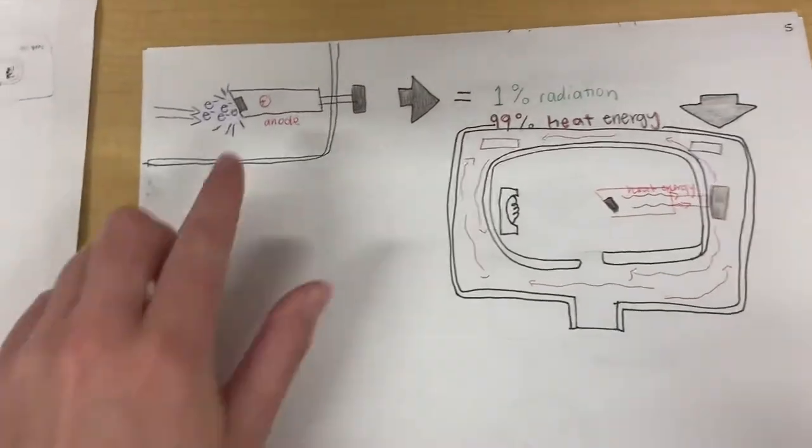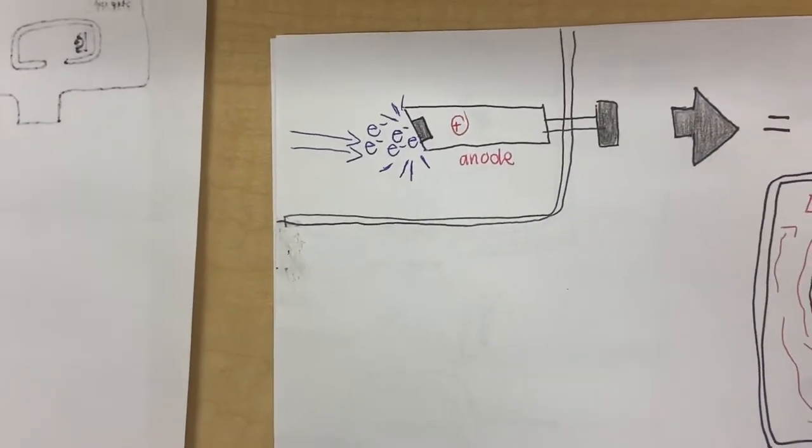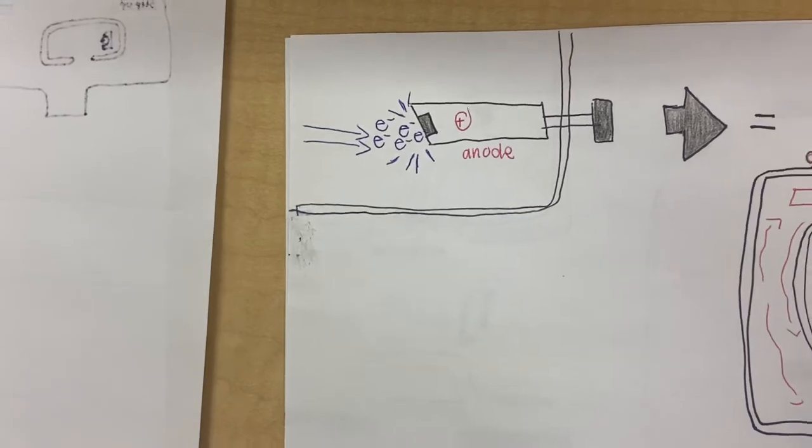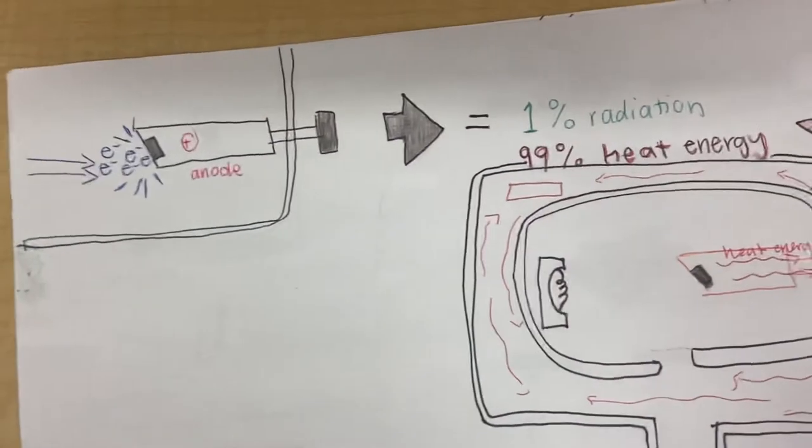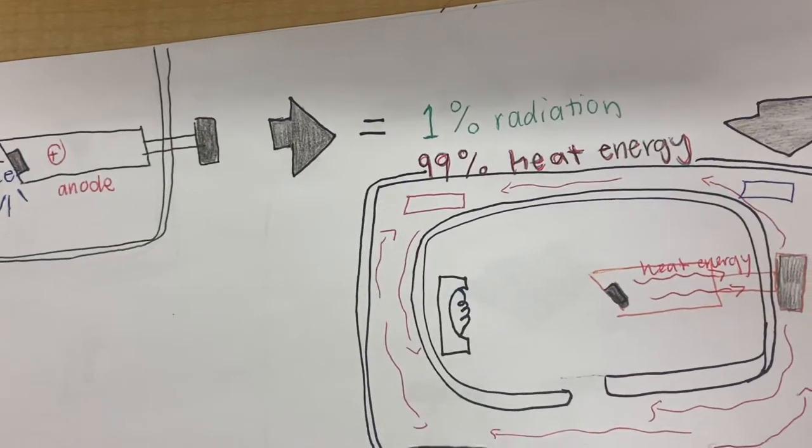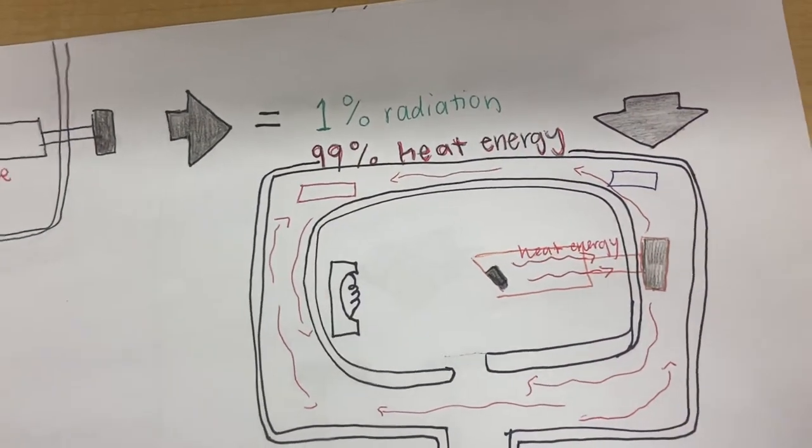Going on, the electrons will then collide with the tungsten target at the end of the anode. When the electrons hit the target, it results in X-ray radiation. Out of all the kinetic energy, 1% will be radiation, and the other 99% will be lost in heat energy.